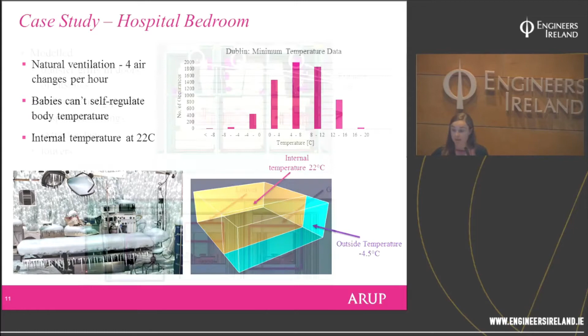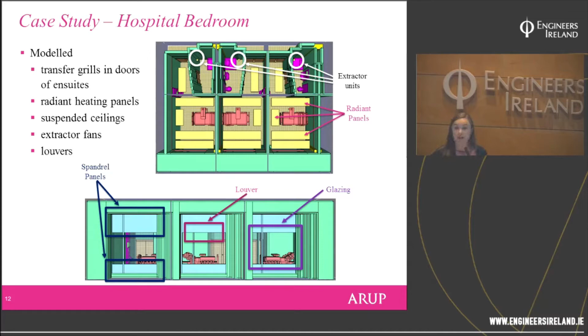We found the outdoor temperature would be about -4.5 degrees in winter, and applied that to our model, which included all the other important elements: the radiant heating panels on the suspended ceiling, the various extraction points, the fans in the ensuite toilets, and the louvers themselves. We modelled all of this and found that the bedrooms were not going to be warm enough, at best reaching 17 or 18 degrees Celsius with the windows open during winter.